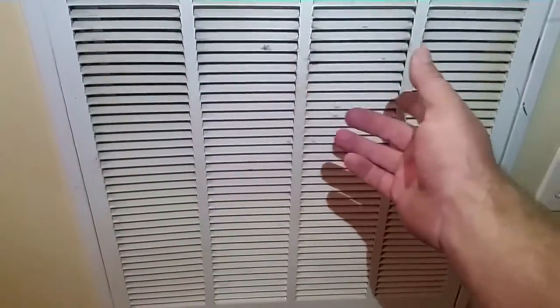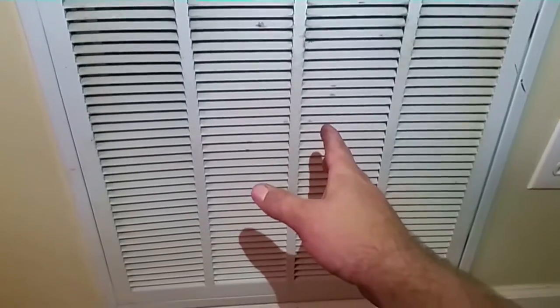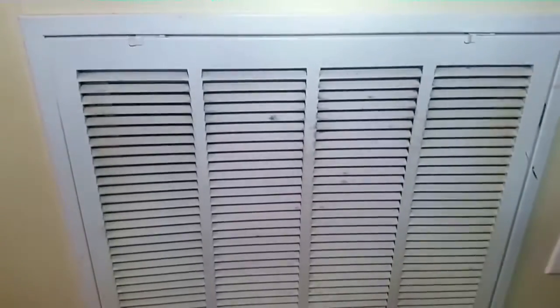This is a 20 by 20 grill. We're going to use about a 0.68, 0.7 K factor for this grill. Check it out. Based on some of my previous experience, we're going to see what kind of airflow we have coming across this grill.